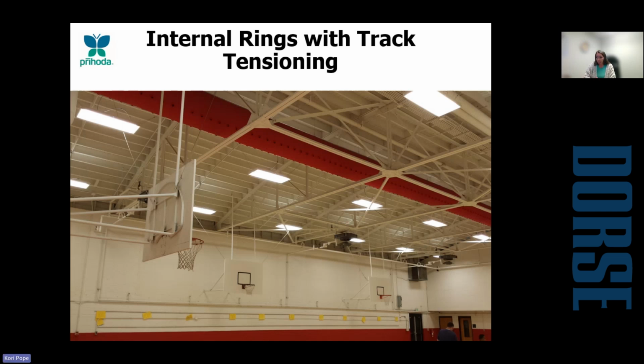So I'd like to point out here that this duct is running through the truss here. So if we did not have anything holding the duct open, it would sag, and at each point where the duct is making contact with something, eventually wear and tear would happen there. So one thing that we always keep a mindful eye on here in the office when we're looking at plans is where's the duct running, and is there going to be anything that could potentially make contact with our ductwork.